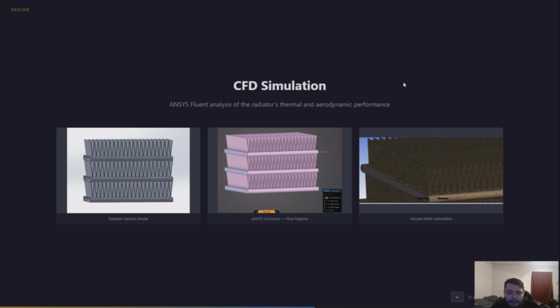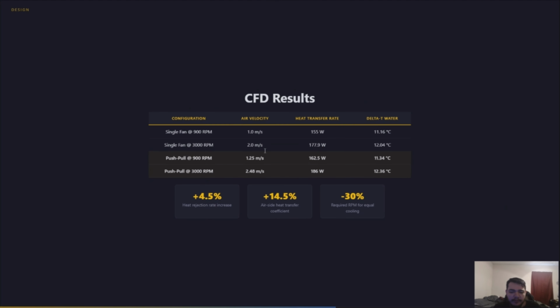The simulations ran 4 scenarios comparing single fan versus push-pull configuration at both low and high RPM. The CFD results confirmed our analytical predictions. At maximum RPM, the push-pull configuration increased the heat rejection rate by 4.5% and the airside heat transfer coefficient by 14.5%, but the most significant advantage is acoustic.